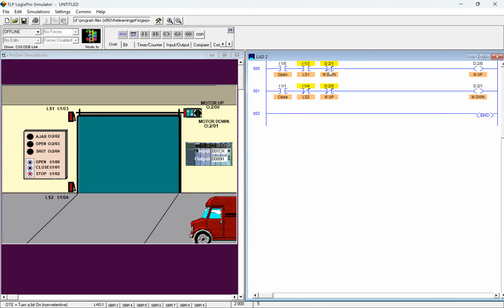What I do is I add in a set of contacts or a relay, depending on the type of starter I have. Using the Square Ds, they don't have auxiliaries on them, so you have to add a relay out there to do it with. But the modern versions, like the modern Allen Bradley stuff, you can actually clip additional contacts on the front of it. So you can add more of these on there if you want.